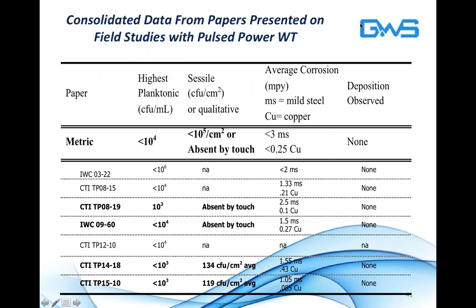Let's look at some data as proof in the pudding as far as what Griswold water systems technology can provide. This is from a set of field studies with pulse power water treatment presented at ASHRAE a year ago. It went back and looked at a set of papers examining the highest planktonic counts, sessile - which would be the biofilm - corrosion, and any deposition.